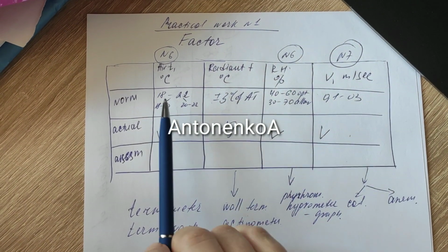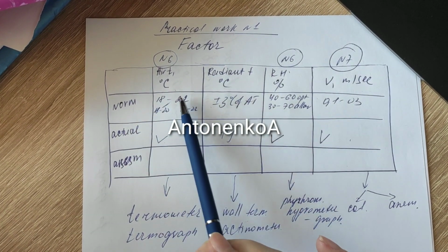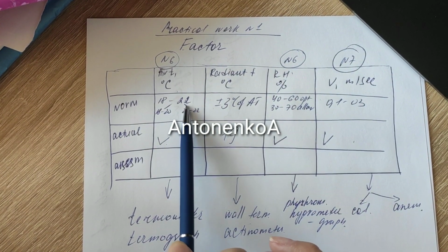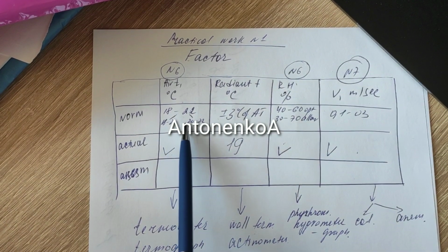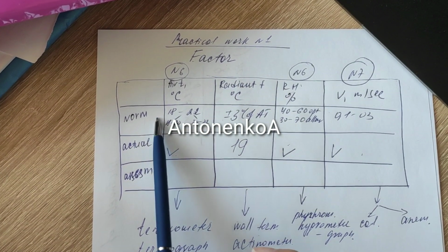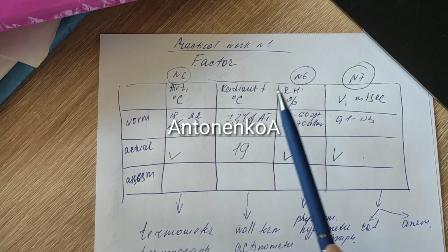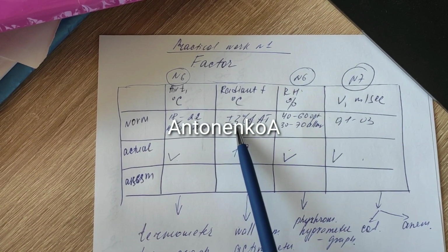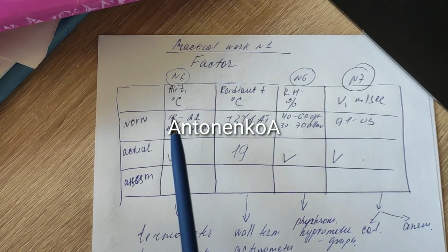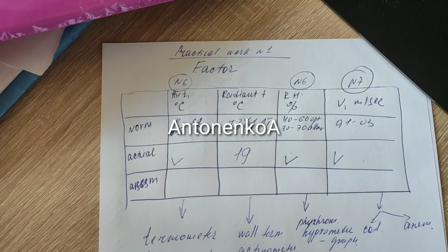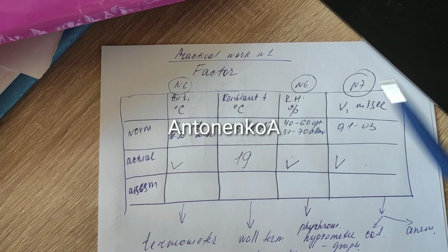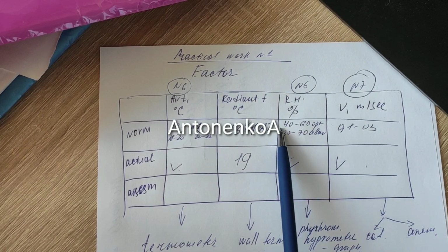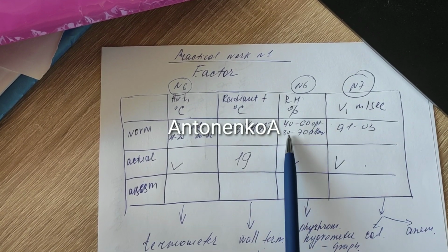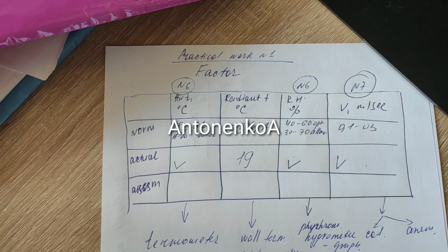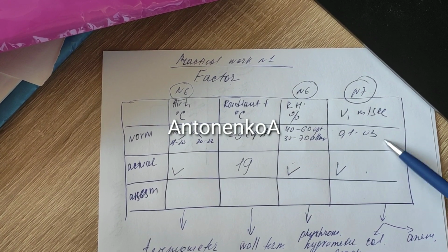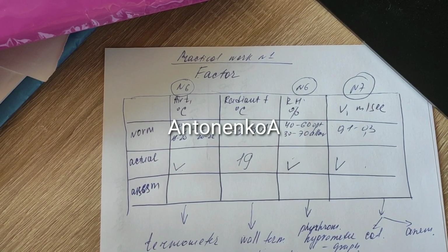And then normal values. Remember that air temperature normal values are from 18 to 22 degrees: for the cold period of year, better 22, warm period of year 18 to 20. Radiant temperature is plus minus 3 degrees from the air temperature. And relative humidity, optimal, the best variant from 40 to 60, but allowable from 30 to 70. And air movement speed from 0.1 to 0.3.